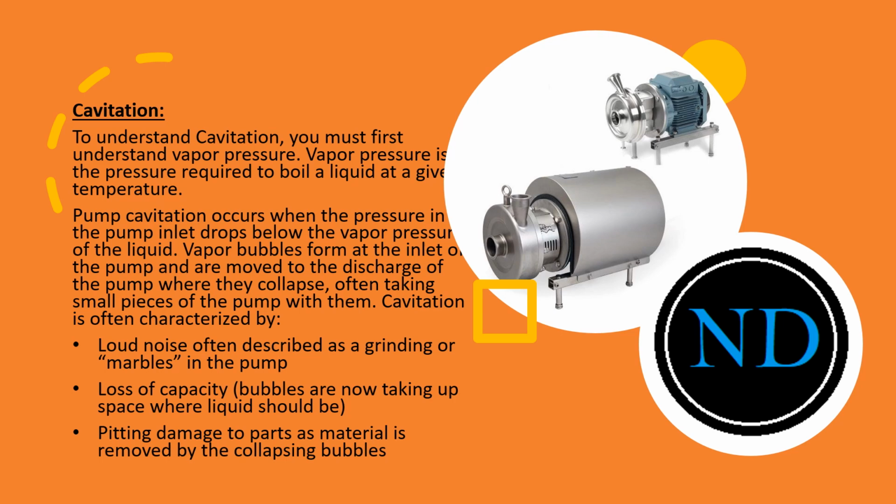If there is no NPSH available properly as defined by the vendor or pump supplier, there will be cavitation. Cavitation, you can observe in the pump suction. Many times you have observed that there is a lot of noise like grinding or some marbles or some particles inside the pump. It indicates that there is some cavitation inside the pump.